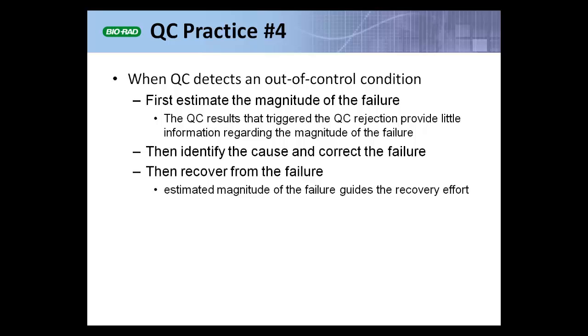There are many ways to estimate magnitude. An obvious easy way would be to run additional replicates of quality control material and take the mean difference between what you're getting in the replicates and the target value. Once you've estimated the magnitude, go ahead and identify the cause and correct the failure — and because you've estimated the magnitude, your approach to recovery is better informed and more cost-effective.